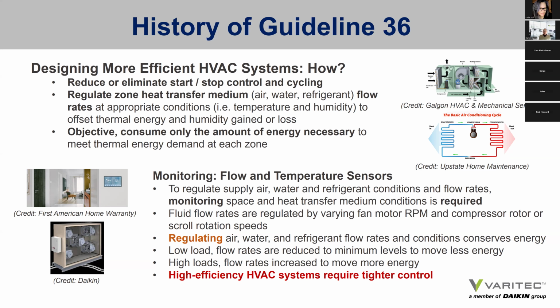Regulating air, water, and refrigerant flow rates and conditions conserves energy because you can now use only the work necessary to provide the heat transfer medium needed to discretely satisfy loads, whether they're at low load or high load. So low load conditions result in low flow rates, high load conditions result in increased flow rates. And a high efficiency HVAC system needs to provide tighter control to do this efficiently.